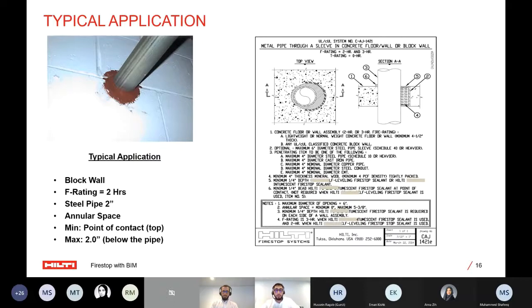Then it would have a sketch or a drawing to show the different items in that fire stopping system. So you can see that number 1 gives you a description of the floor or the wall, and this floor or wall can be 2 hours or 3 hours fire rated, and it could also be a block wall. Number 2, optional to have, is a 6-inch diameter steel pipe. And then number 3, which is the penetrant, and this is very important, is telling me that I can use this system for a maximum 4-inch diameter steel pipe, or a cast iron pipe, copper pipe, steel conduit, or EMT. And you can see that even if I'm looking at a steel pipe, it's also considering what the schedule of that pipe is as well.